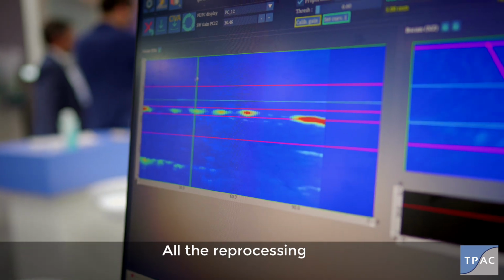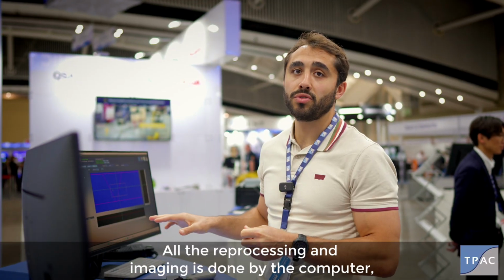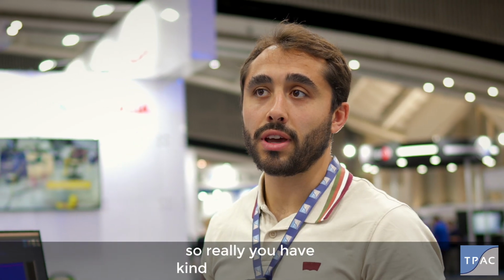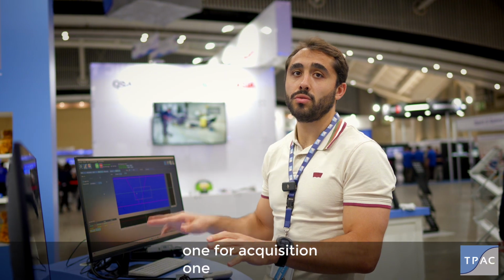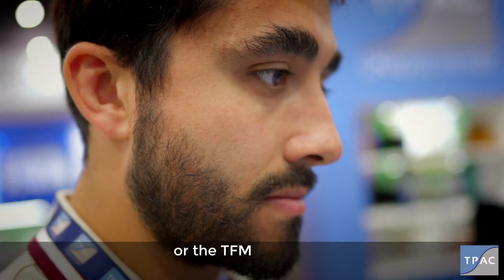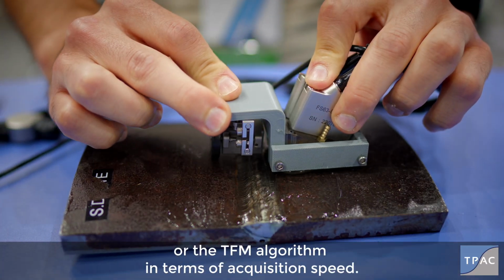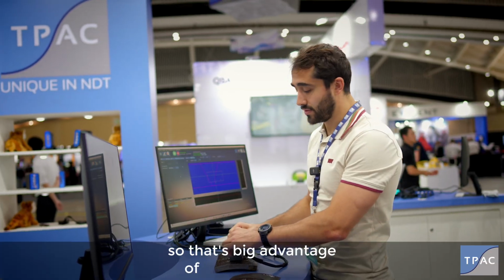All the processing and imaging is done by the computer. So really you have kind of two pipelines, one for acquisition, one for processing. So we are not limited by the processing or the TFM algorithm in terms of acquisition speed. So that's a big advantage of that technology.